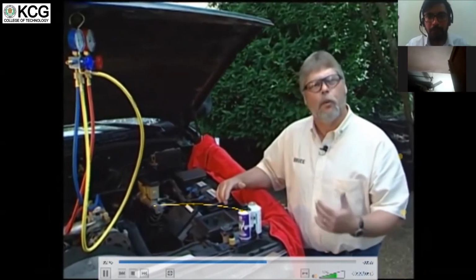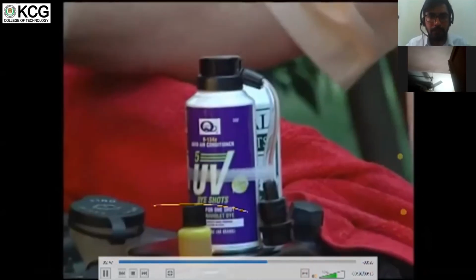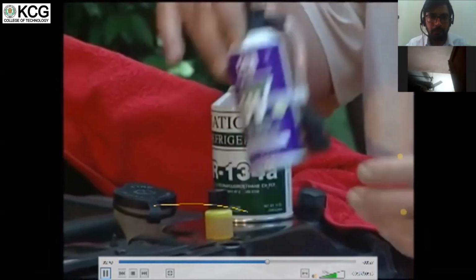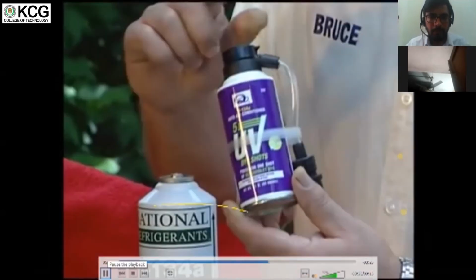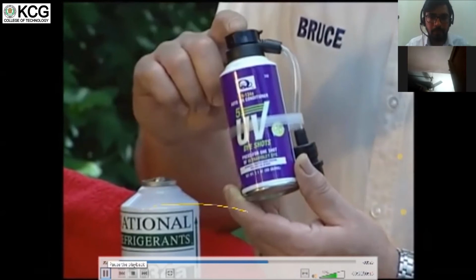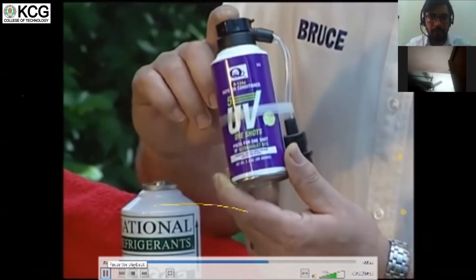Once the dye is in there, what we want to do is leave the AC on high, let it run for about 30 minutes, and then we can shut it off, take our UV light, and we've got some special UV glasses. We're going to go around all the hoses, all the connections, see if we can pinpoint where that leak is. Okay, at this point, I've pinpointed the leak.